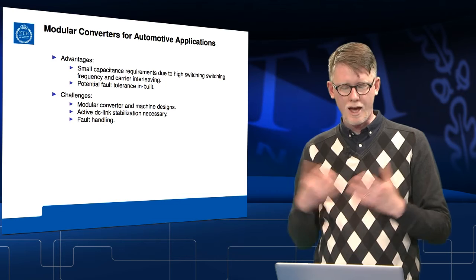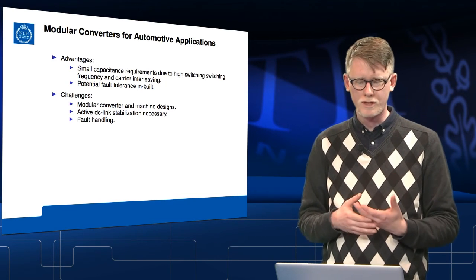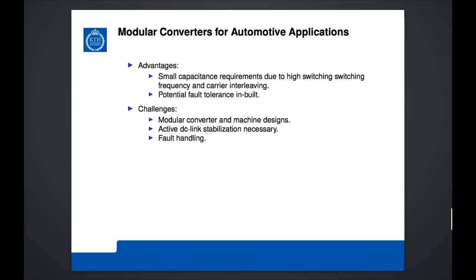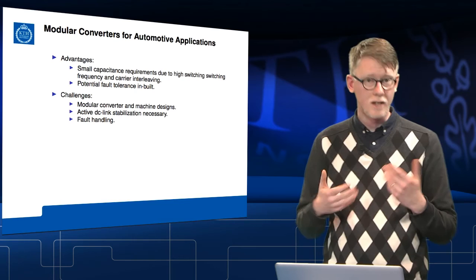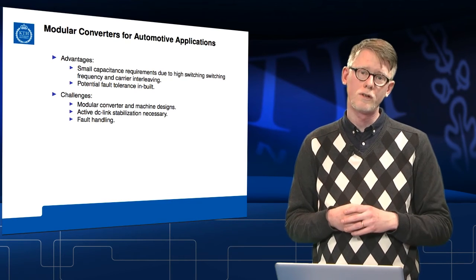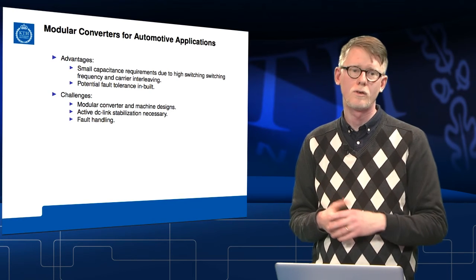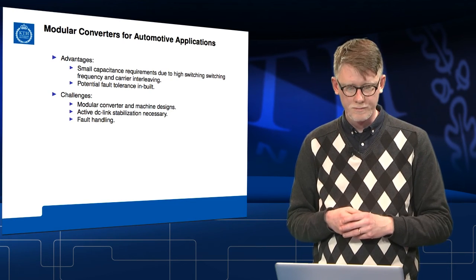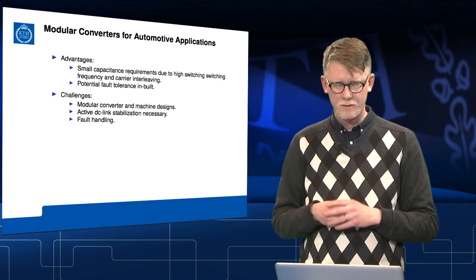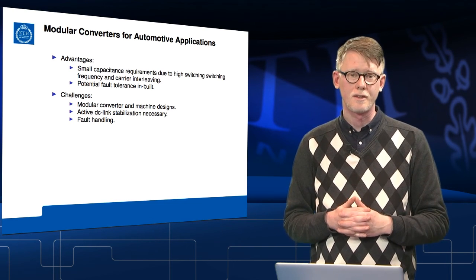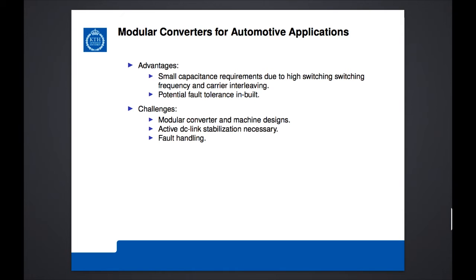Modular converters have the advantage of reduced capacitance requirements due to the high switching frequency and the ability to phase shift and interleave the carriers. I haven't talked about it, but due to the modular nature, we also have inherent fault tolerance: we could design the converter so it can still operate if one or more sub-modules fail. The challenge is to obtain a solution that is truly competitive, which requires designing a modular converter and a corresponding electric machine at the same time.